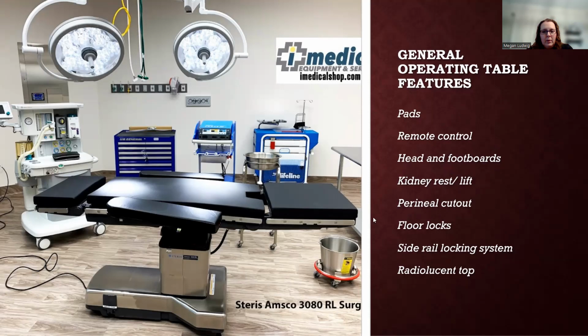So the hole right there is called the perineal cutout, to access the perineum. It does lock in place. It raises and lowers. You can raise the head up so the feet are down, or vice versa, feet up, head down, Trendelenburg. You'll learn your different positionings. Another important thing is that it has a radiolucent top. That means if we bring in a portable X-ray machine or a C-arm, for ortho or neurovascular cases usually, the X-ray can penetrate through it so we can see the patient's bones or vessels or whatever it is we're doing. The X-ray won't be blocked by that. So it is radiolucent. The X-ray goes through it.